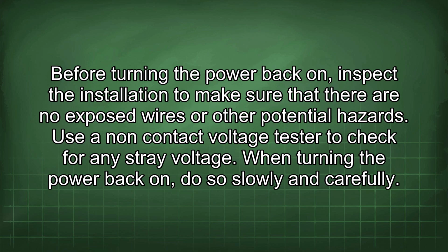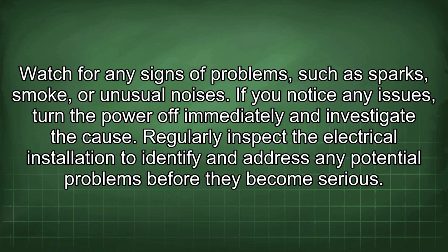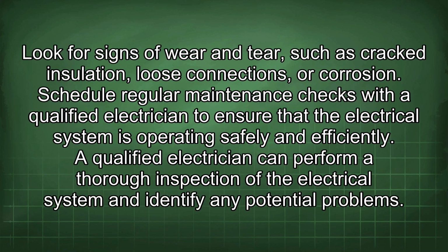When turning the power back on, do so slowly and carefully. Watch for any signs of problems, such as sparks, smoke, or unusual noises. If you notice any issues, turn the power off immediately and investigate the cause. Regularly inspect the electrical installation to identify and address any potential problems before they become serious. Look for signs of wear and tear, such as cracked insulation, loose connections, or corrosion.